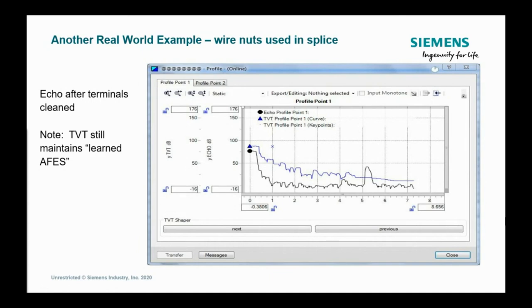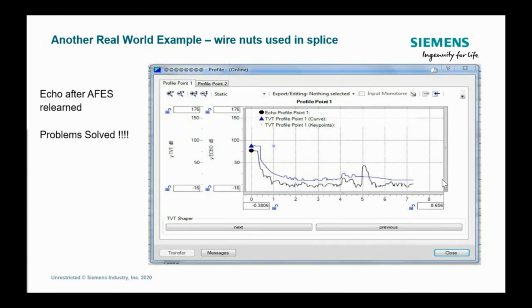changed it so it was ringing down to the noise floor. One of the things you'll notice, though, is that the TVT curve still remained the same as it was before. In other words, they had done a learn for auto false echo suppression in an attempt to fix this, and it remembered that learned TVT. So guess what? We went in, did an auto false echo suppression again, and once we did that, all of a sudden you got a nice clean system and problem solved. That was actually back in 2015 that we pulled this out. I haven't heard from that site since.